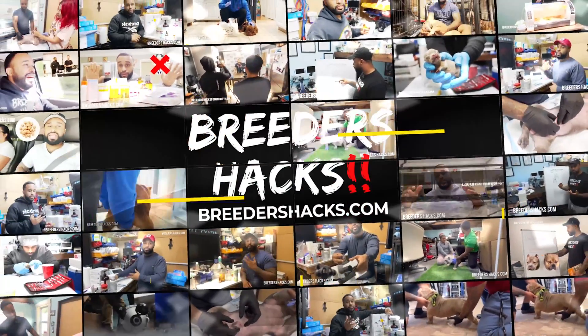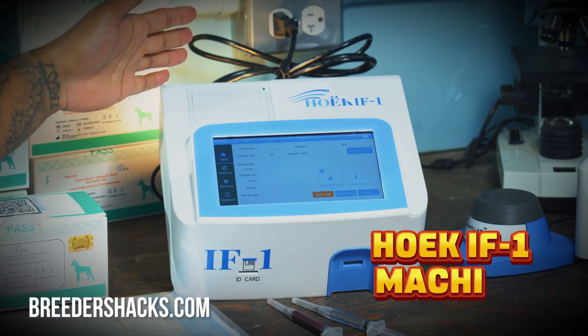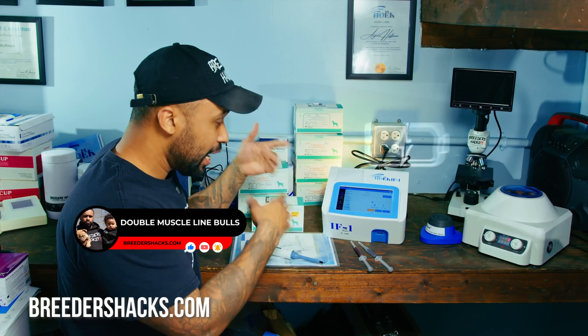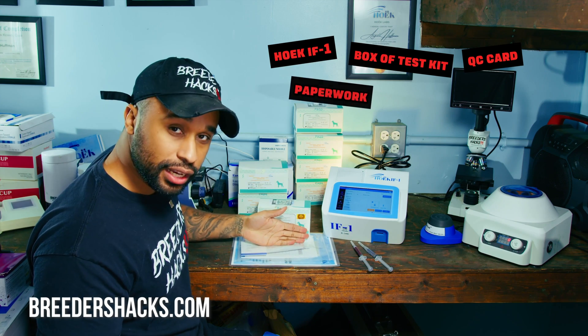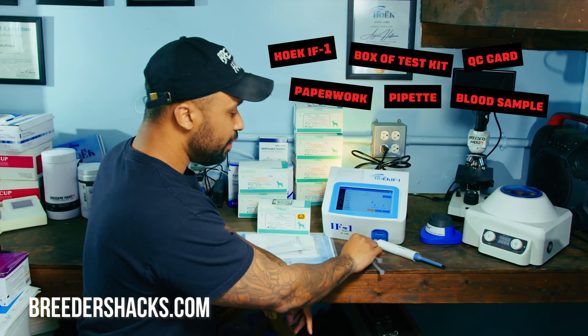We're going to go ahead and get right into it. So the Hoek IF-1 machine — when you open up your machine, go ahead and plug it in and charge it. The great thing is it's actually portable, so you can disconnect the charger after it's charged and take it on the go. The things that you need are: your machine, a box of tests, your quality control card, all the paperwork that comes with your machine, a pipette, your blood sample, a vortex mixer, and a centrifuge. Typically all this comes in a bundle when you buy a machine from a place like BreedersHacks.com.